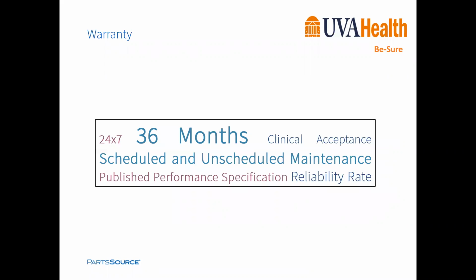I would also just make sure that whenever negotiating a warranty that we are ensuring that warranty is in force 24/7, because we don't want to have defects occur outside of the warranty period and then have vendors not accountable for them because they occurred outside of some Monday through Friday 8 to 5 terms that might be specified by the vendor. In this case, we expect throughout that period the equipment to meet its published performance specifications. And this is important because what you'll find from many vendors is they do not have any reliability rate or data, and as a result, they're very concerned about going on record about performance. In some cases, we have needed to establish performance expectations to be part of the contract because the vendor could not provide us with performance data that would allow us to measure the system's performance.